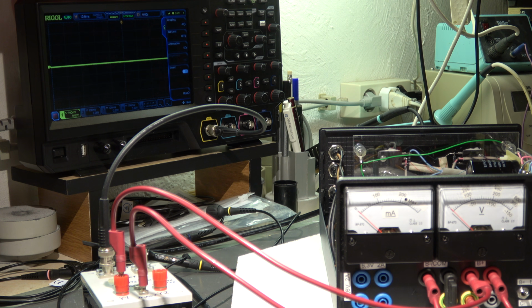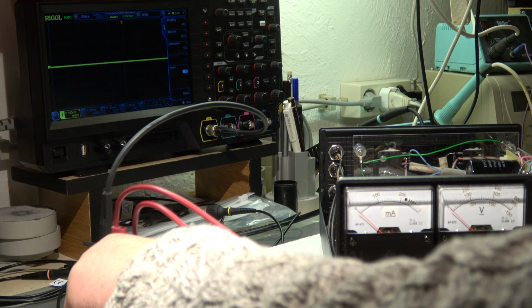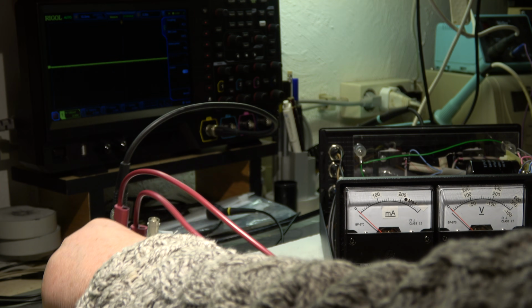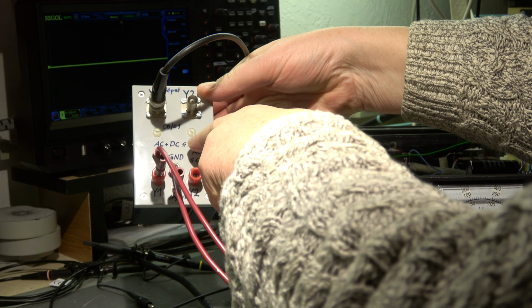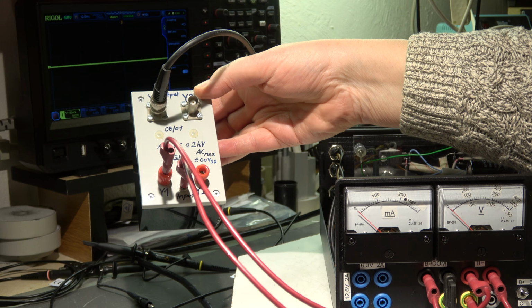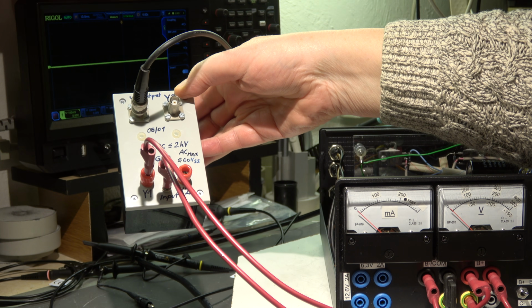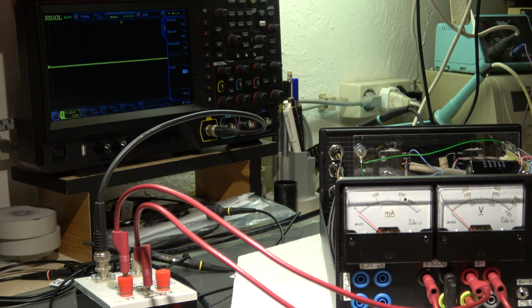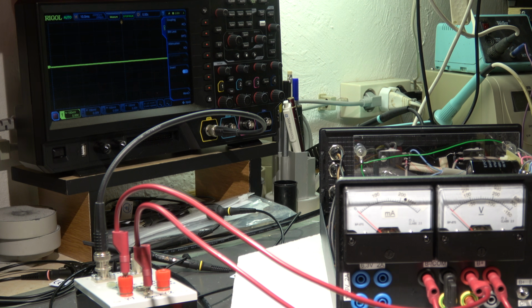The measurement of output ripple and noise is done with this little adapter. It's homemade, from 20 years ago. It's more or less only a coupling capacitor inside, rated up to 2 kV, with overvoltage protection too, so the maximum voltage is 60 volt peak. Frequency range is, I think, starting at 10 or 20 hertz up to some hundreds of hertz or kilohertz range. It's especially made for ripple measurement.